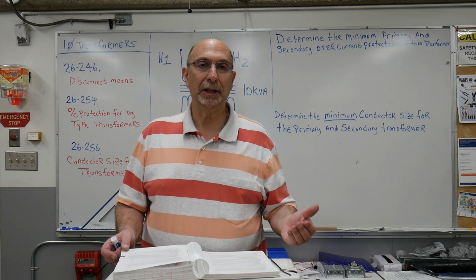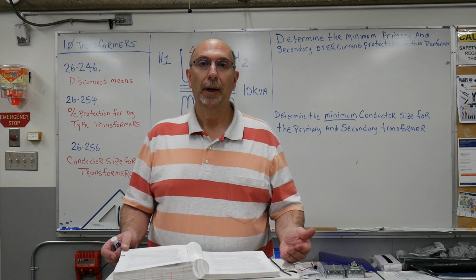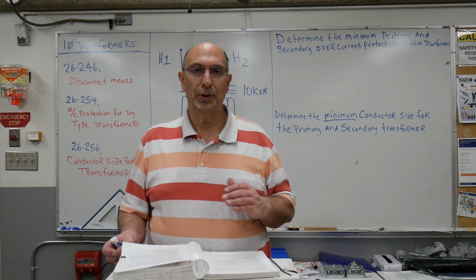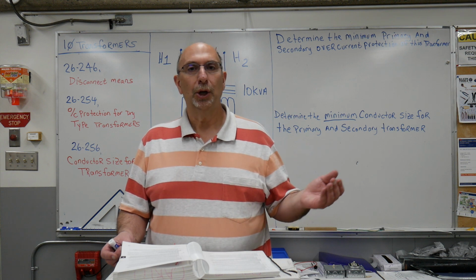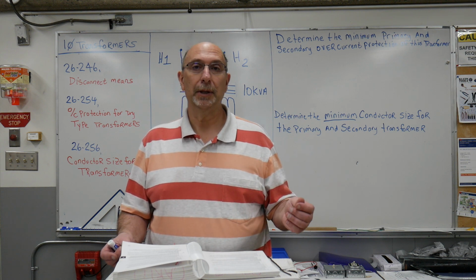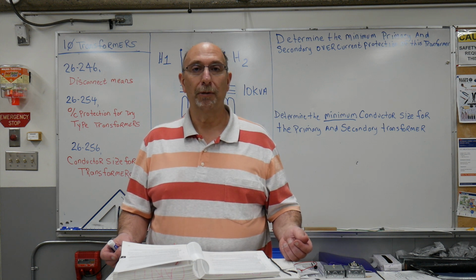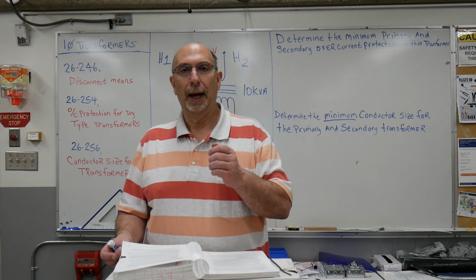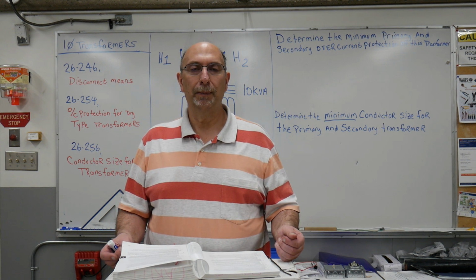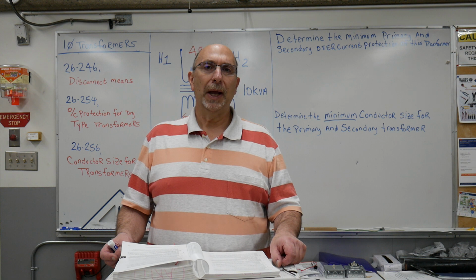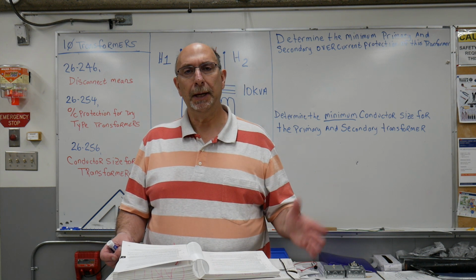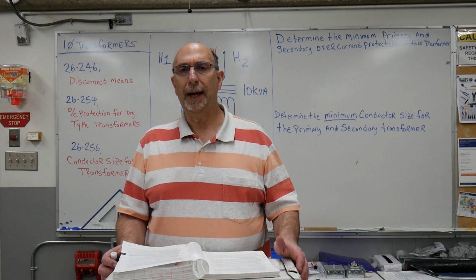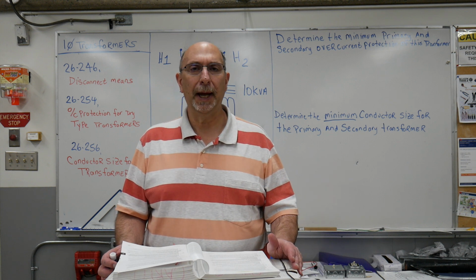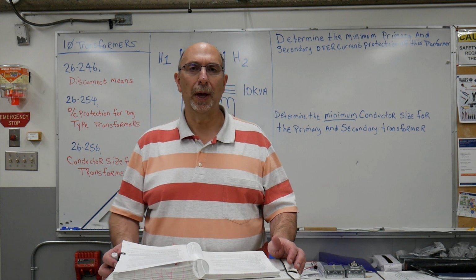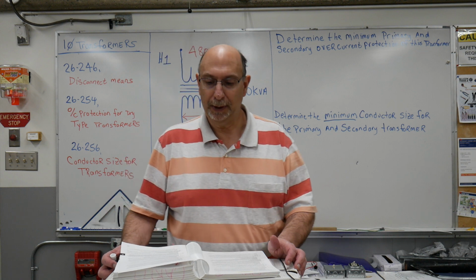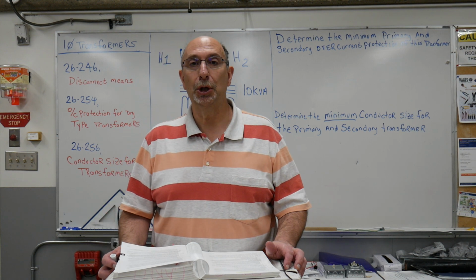So we also have to deal with tables 1, 2, 3, and 4 of the code book. As transformers get larger, you may be feeding them with single conductors, which relates to tables 1 or 3: copper single conductor is table 1, aluminum is table 3. With smaller transformers, for example 10, 12.5, 25 and 50 kVA, we would be feeding them with 2-conductor or 3-conductor cables, so we would be using either table 2 or 4.